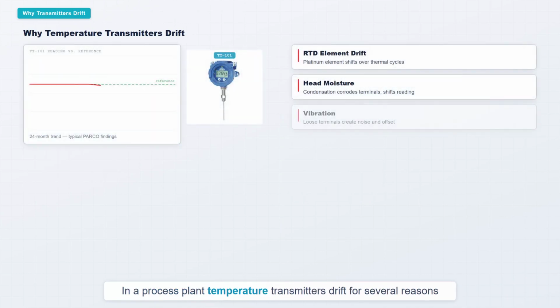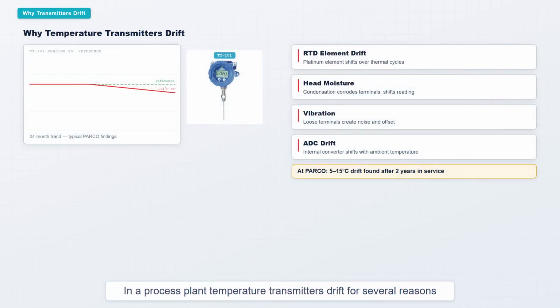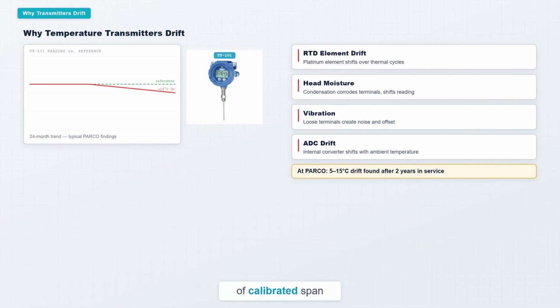In a process plant, temperature transmitters drift for several reasons. The RTD platinum element drifts over years of thermal cycling. Moisture entering the head corrodes the sensor terminals and shifts the resistance reading. Vibration from nearby pumps or compressors loosens connections. The transmitter's internal analog-to-digital converter also drifts with ambient temperature. At Parco, we routinely find transmitters that are off by 5 to 15 degrees after 2 years in service. Calibration restores the transmitter to within its specified accuracy, typically plus or minus 0.1% of calibrated span.